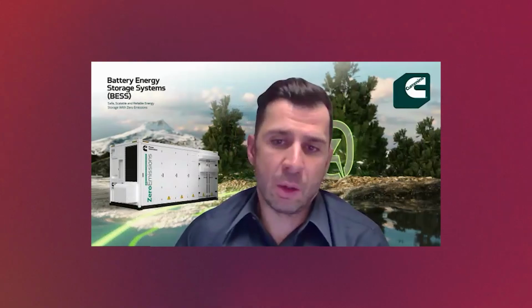A battery degrades over time. So today, a battery that is 2 megawatt hours, in 6 months we're going to lose a few percentage points, and so on and so forth. So in 10 years, there's a potential that capacity will go down by 30%. So it's at 70%, and this is typically what's considered end of life for a stationary application. So it's very critical when you're specifying a battery.